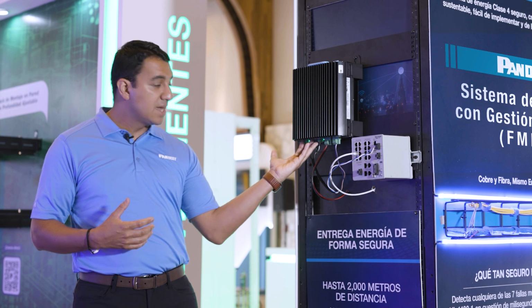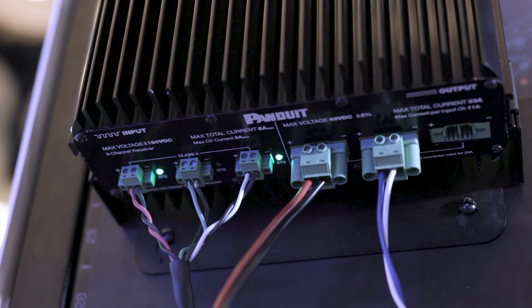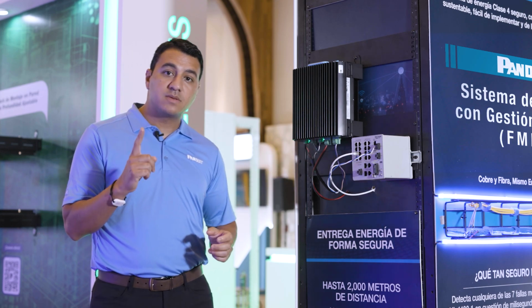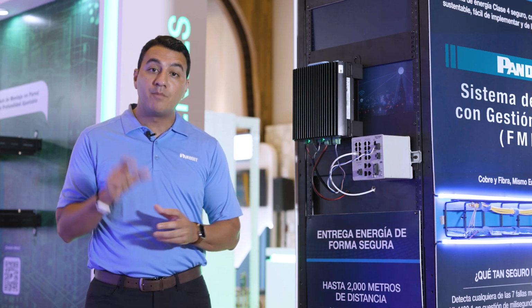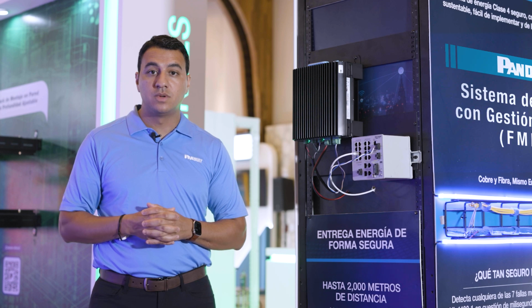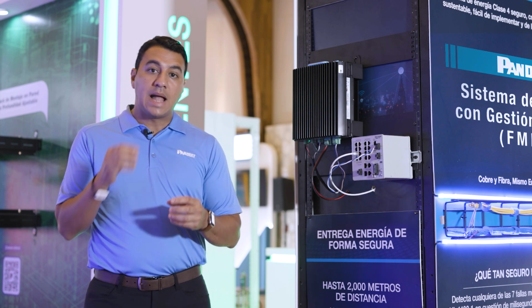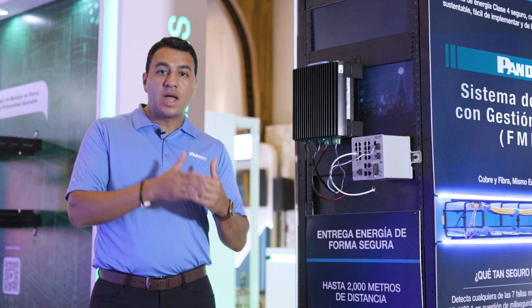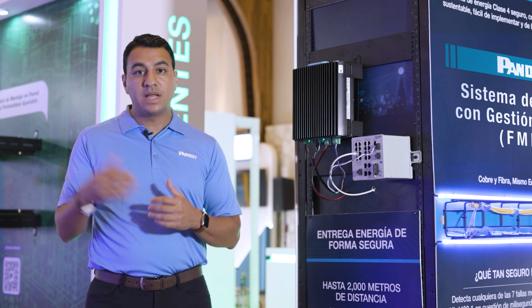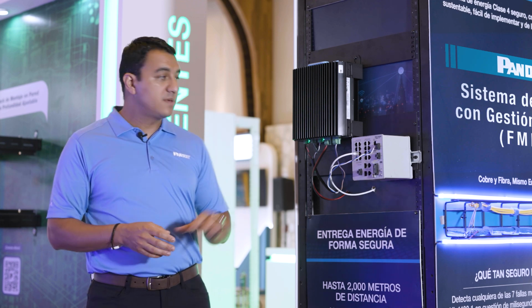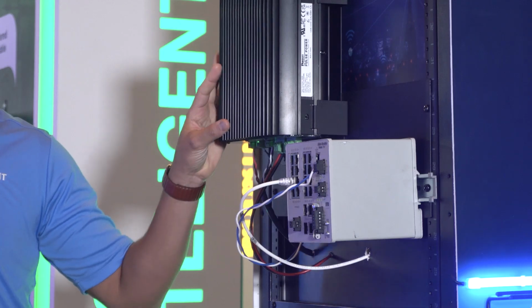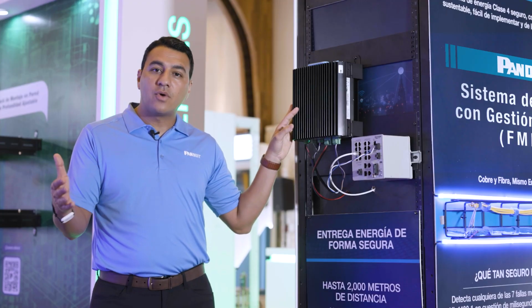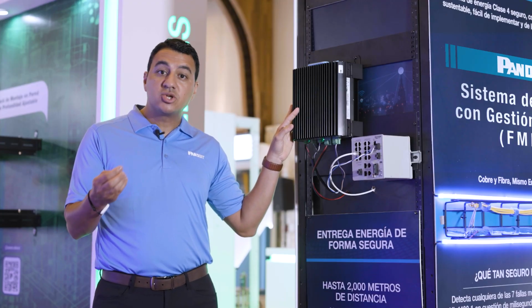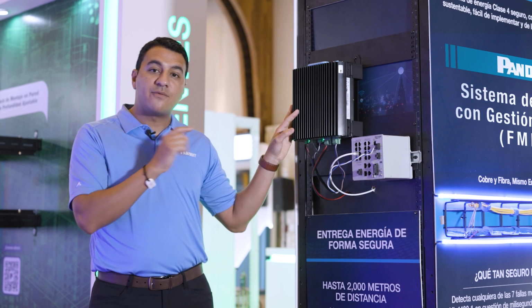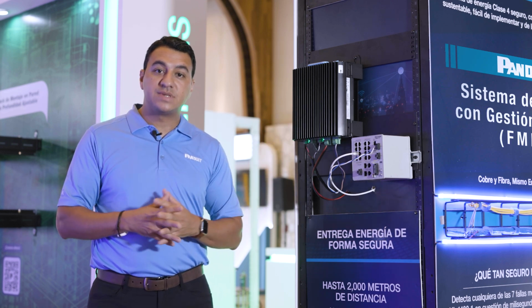The receiver has 3 input channels and 3 output channels. Each input can connect to a single transmitter module, like the channel that I showed you. Each module outputs 600 watts. You have to account for losses in the cable and the distance that you're going until you get to the receiver. But as a rule of thumb, if you're going about 400 meters using 16 gauge cable, you can expect to get about 530 watts out of the receiver.